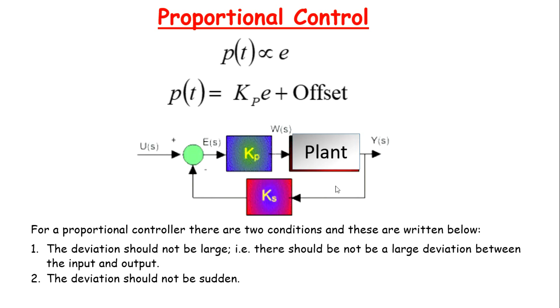When the proportional band is too high, a large error is required to make necessary changes. When the proportional band is too low, a small error causes a large change in output that overcompensates. This can send the system oscillating out of control. Small values of proportional band, that is high gain, are usually referred to as a narrow proportional band, whilst low gain is termed a wide proportional band.